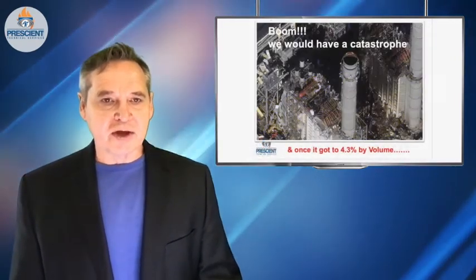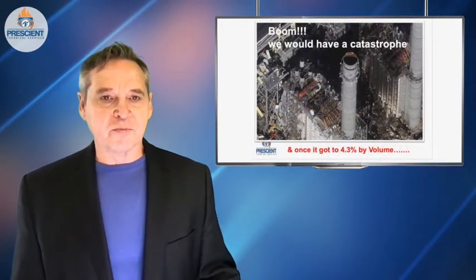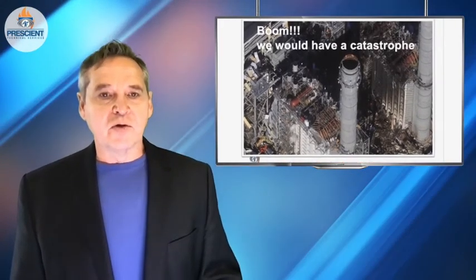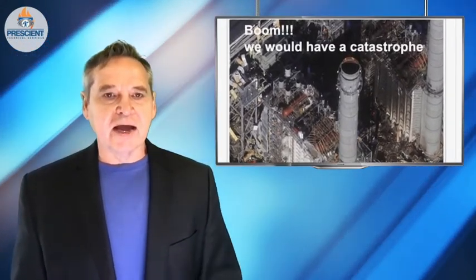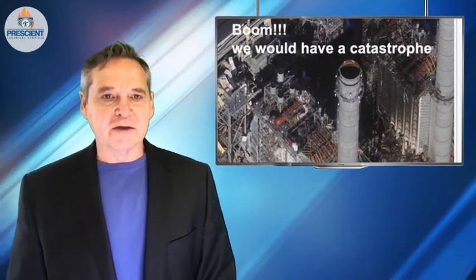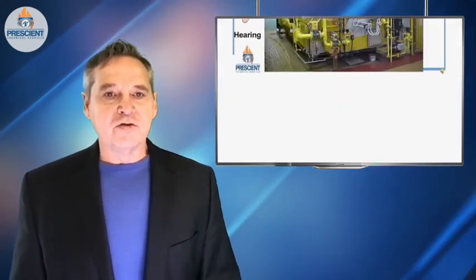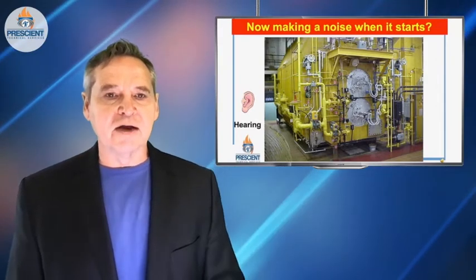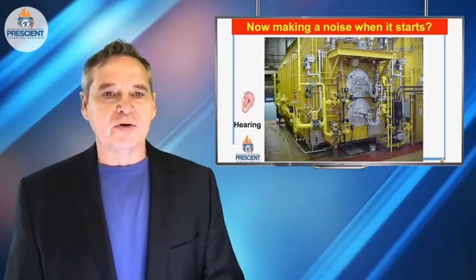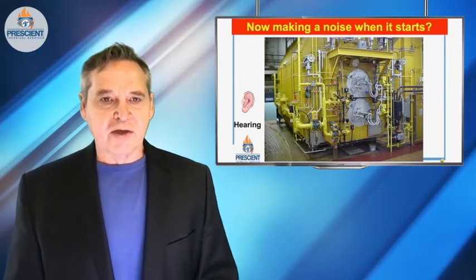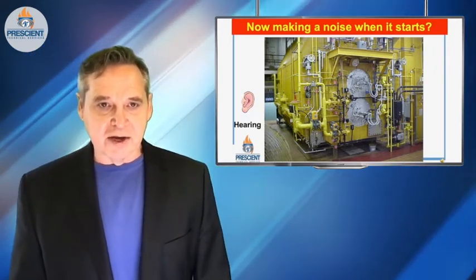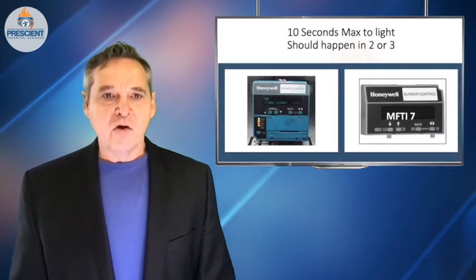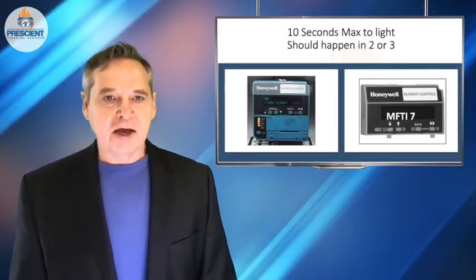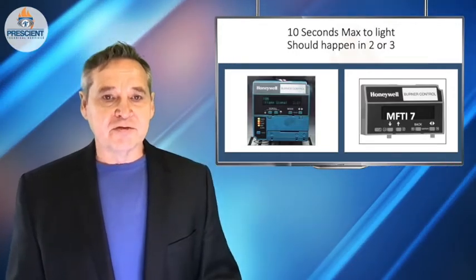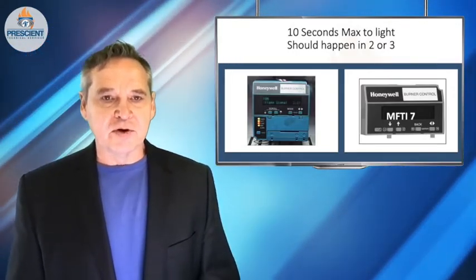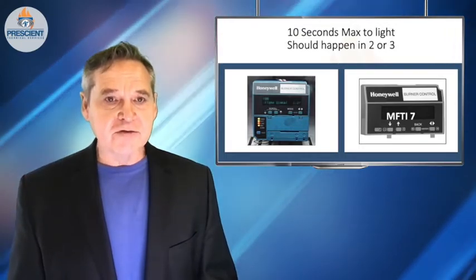And then during one of those light-off attempts, when an ignition source like a spark igniter occurs, there will be that huge explosion, that catastrophic incident that will likely send metal flying in all directions. You should also be aware that it's not only light-off attempts, but it's an audible light-off that you should be careful of. That whoomph sound after you light off is not a good thing. When the actual light-off occurs, how many seconds go by after there's an ignition source introduced is also an important factor.